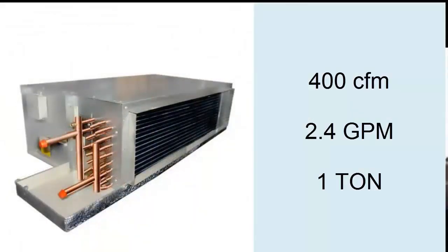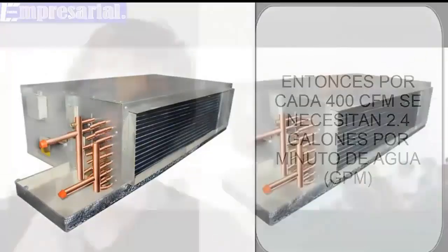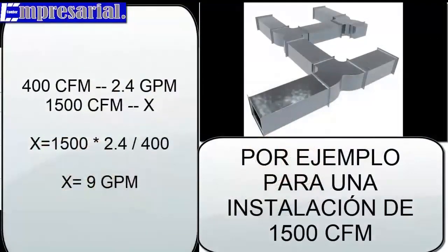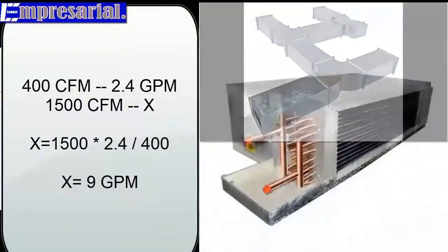In this case, 1500 CFM are being conditioned. With a simple rule of proportionality, we can know the water flow required by the fan coil. Calculating for 1500 CFM of air per minute, 9 gallons per minute of water must pass through the fan coil.